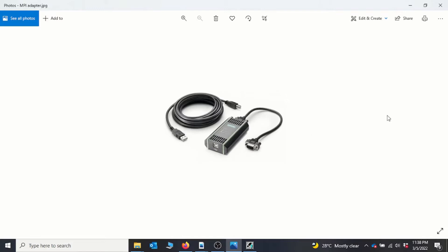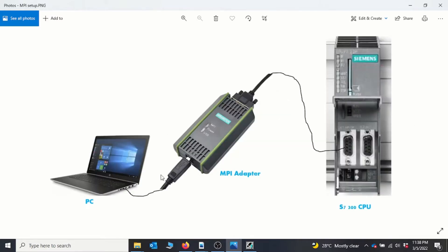The setup is basically like this: you have one end connected to your PC, which holds your Step 7 program, then the MPI adapter sits right in between, and the other end connects to the DB9 connector that comes with the Siemens PLC CPU. With the 300 station and the 400 station you have the same port, but with the 400 station you also have the flexibility of adding a communication processor with an Ethernet port, so you can also program the CPU using the Ethernet port.